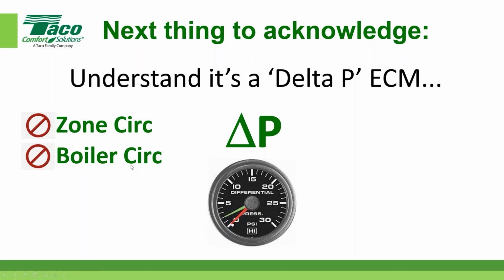Don't use it as a boiler circulator. I already told you why, right? The only two things that want to run a boiler circulator would be either the 0 to 10 volt or pulse width modulation, or some kind of signal from the boiler manufacturer to the boiler primary circulator. Then it can speed up and slow down with instruction from somebody else. You've got to think of it as almost like us, the circulator manufacturer, handing the keys over as far as control is concerned to the boiler manufacturer. So unless that's happening, you want to stay on fixed speed, and you don't want to put it on an adaptable auto mode.